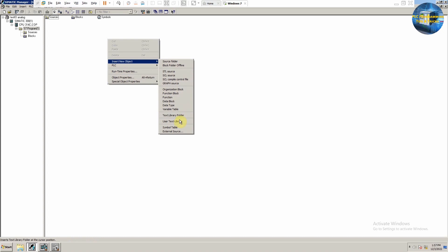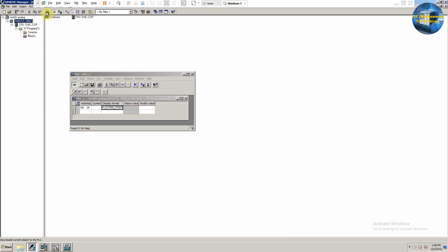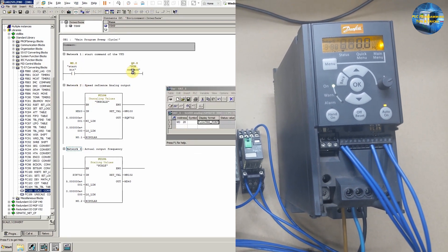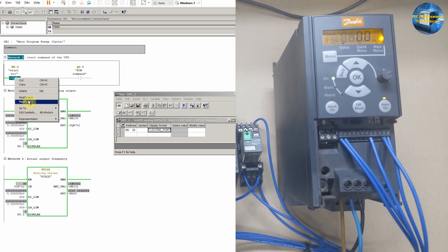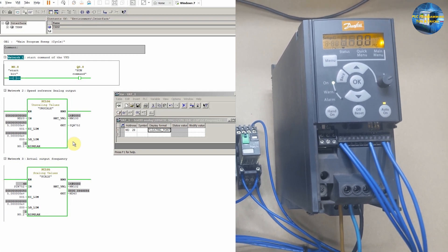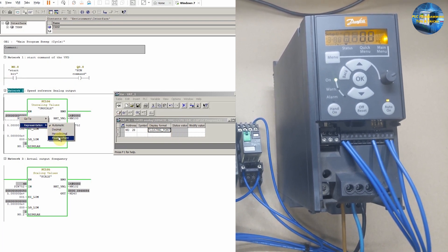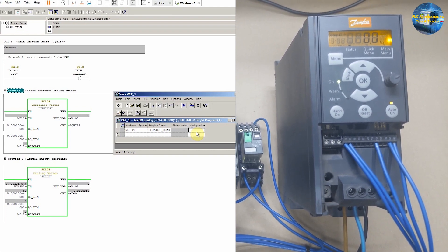Next we will go back and make a variable table, defining MD20 as a floating point data register. We will then download the project to the PLC and see how it works. After downloading, we will monitor the ladder logic. First we will start the VFD by forcing the start bit M0.0 on, which sends digital run command Q0.0 to the VFD. We will change the tag value representation to floating point so we can modify the MD20 data register, which is the speed reference signal for the VFD.